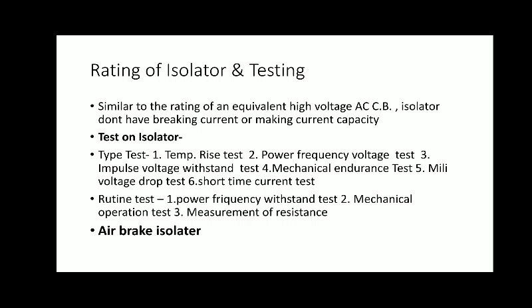The following tests are conducted on isolators. There are different tests conducted on an isolator. First, type tests. In the type tests, there are different tests: temperature rise test, power frequency voltage test, impulse voltage withstand test, mechanical endurance test, millivolt drop test, and short time current test. These are the type tests performed on the isolator. Next, routine tests: power frequency withstand test, mechanical operation test, and measurement of resistance test. So these are the different tests performed on the isolator.